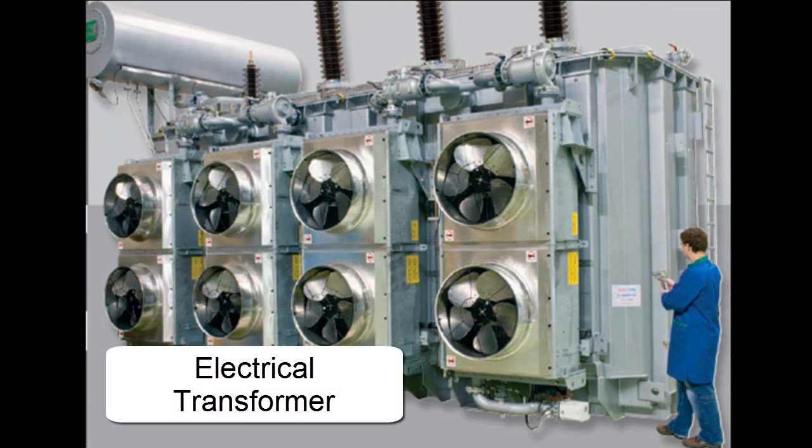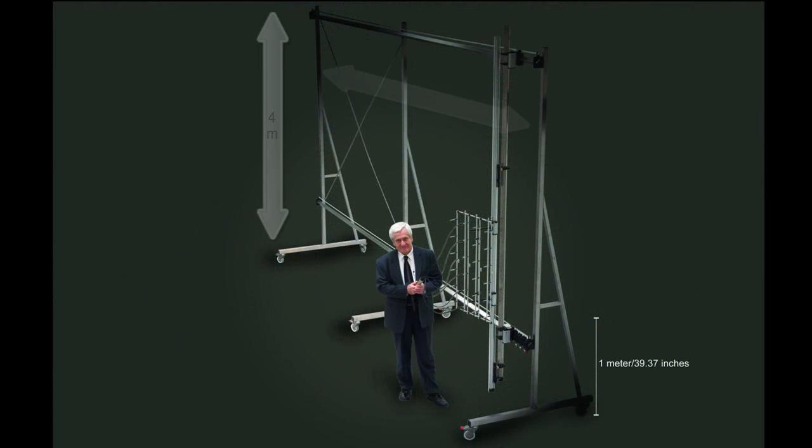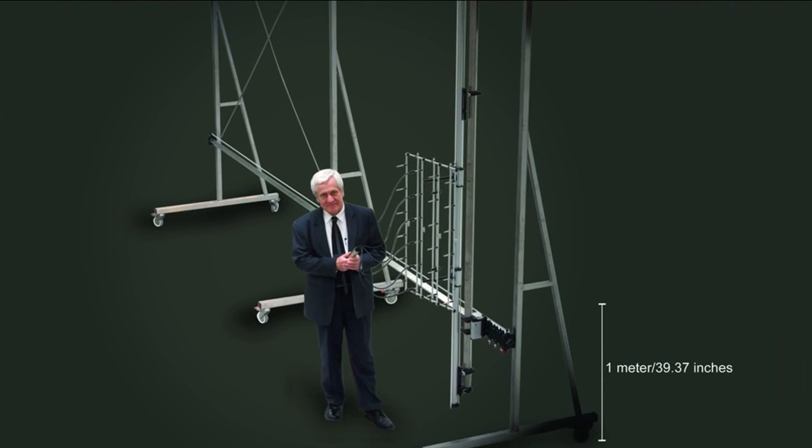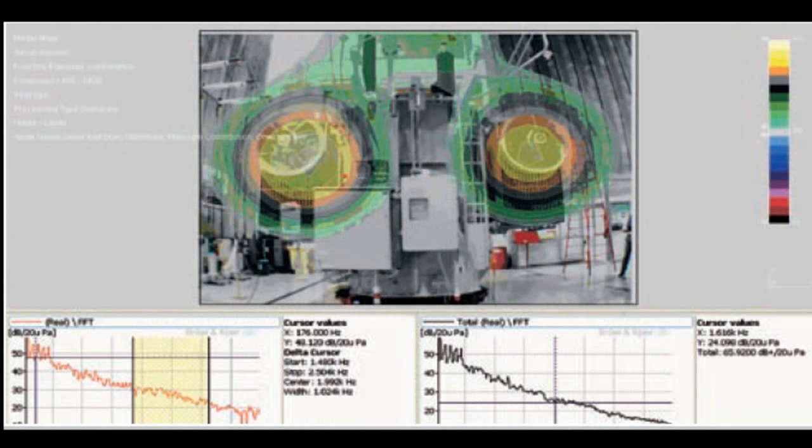And still enable a reliable value of sound power to be determined. The robot shown here is four by six meters, and is used for making scanned array measurements on large electrical transformers, to check the quality of the production by means of a noise map.